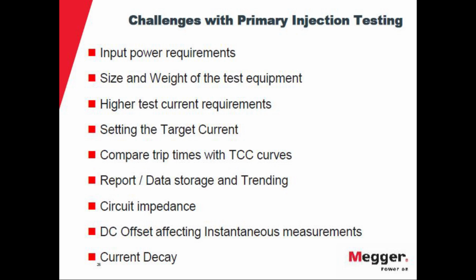Then setting the target current is difficult. Once you set the current target manually, because of heating of the unit or input power problems, your current is going to decay, so you need to adjust manually. The instrument that I'm presenting today takes care of all of these issues, at least from the control side, automatically. It has feedback that adjusts the current automatically and maintains the current during the test without any problem.